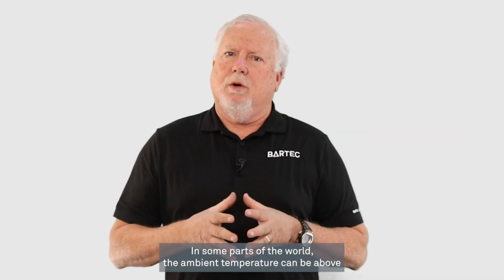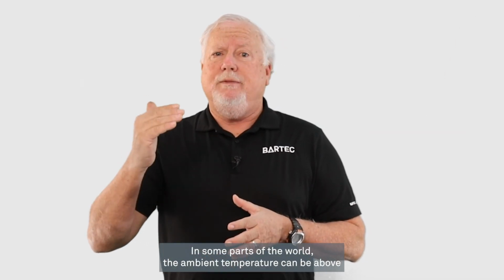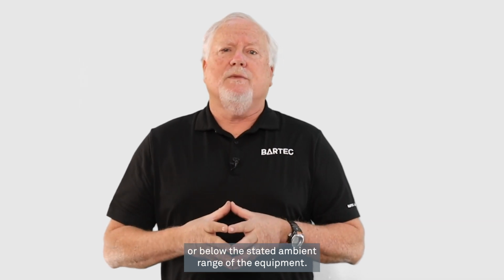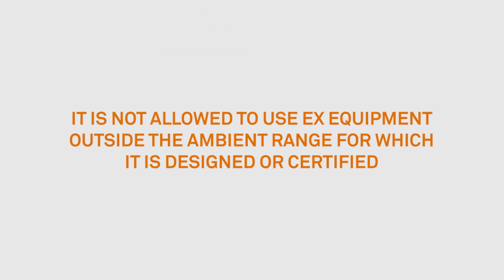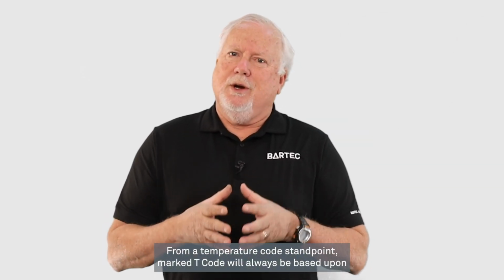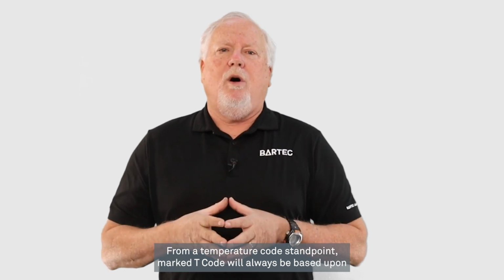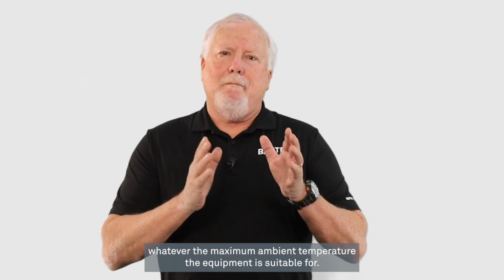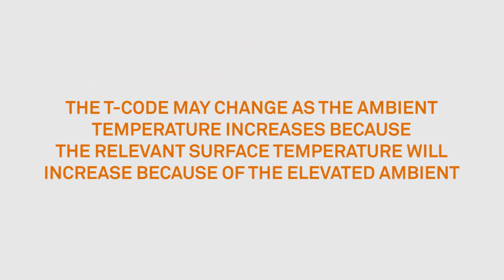In some parts of the world, the ambient temperature can be above or below the stated ambient range of this equipment. It is not allowed to use EX equipment outside of the ambient range for which it is designed or certified. From a temperature code standpoint, the marked T code will always be based upon whatever the maximum ambient temperature the equipment is suitable for. The T code may change as the ambient temperature increases because the relevant surface temperature will increase because of the elevated ambient.